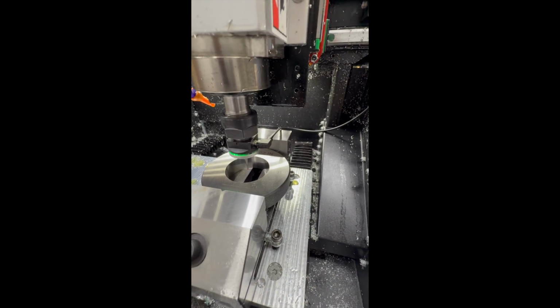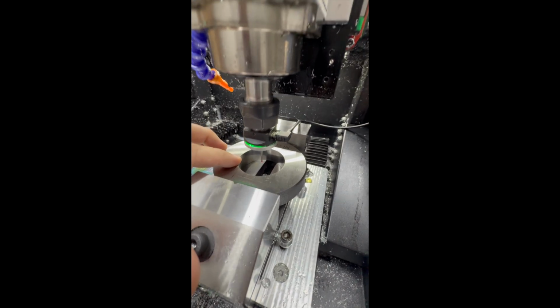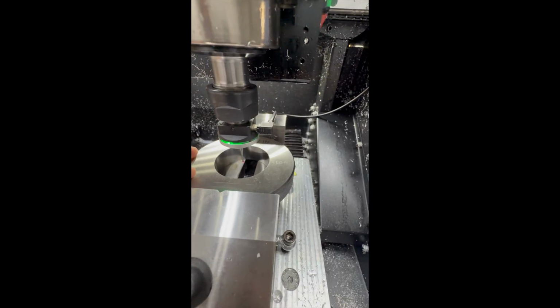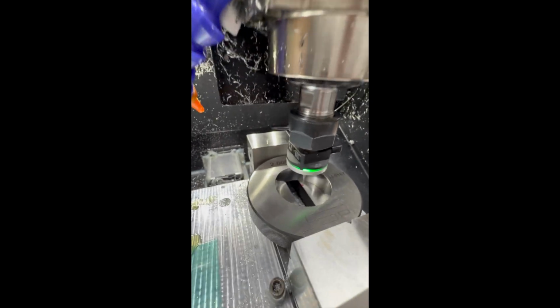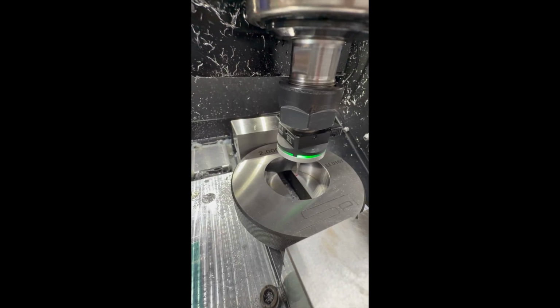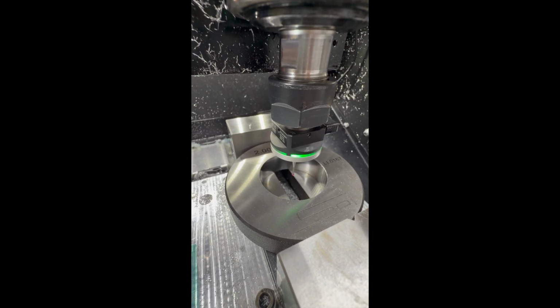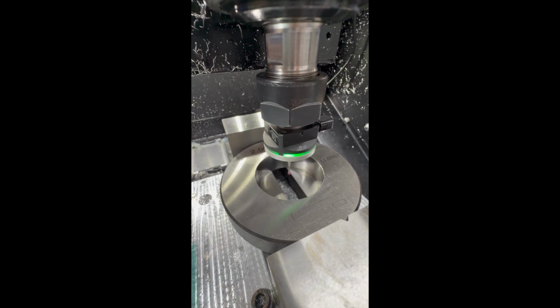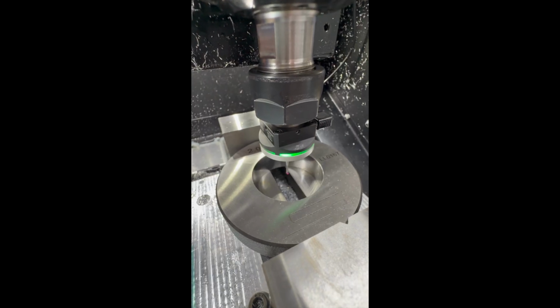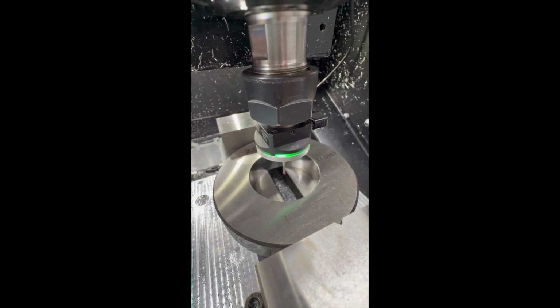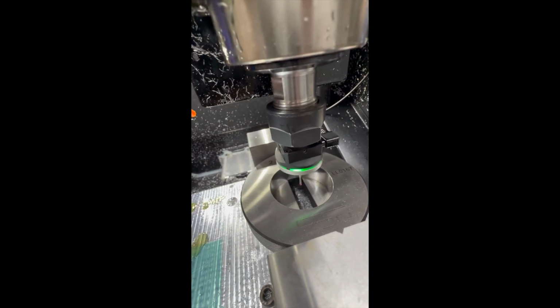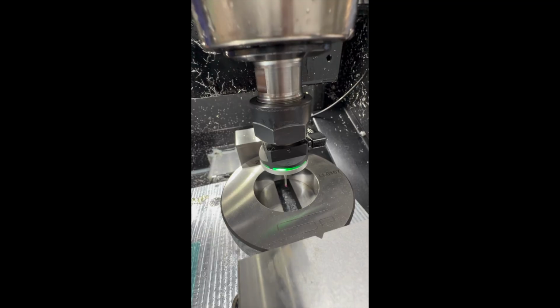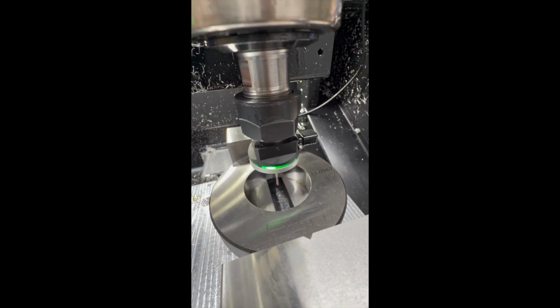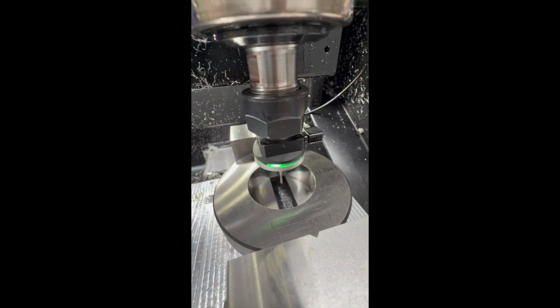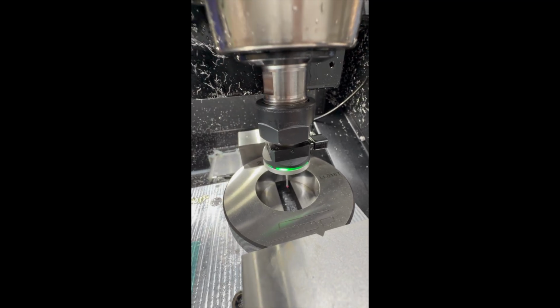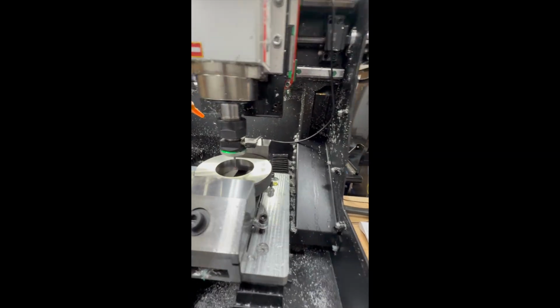With that, I decided to do a couple of tests. First, measure this hole repeatedly until I can get a good size for the effective probe tip diameter. Obviously, the tip diameter is 2 millimeters, but because of the overtravel and everything, it's actually a little bit less than that. I started out with a probe diameter of 1.873 on this machine. It didn't change a whole lot. I got to 1.8849, but let me show you how I ran this test.